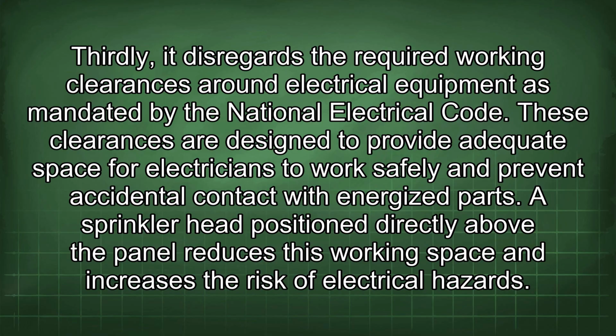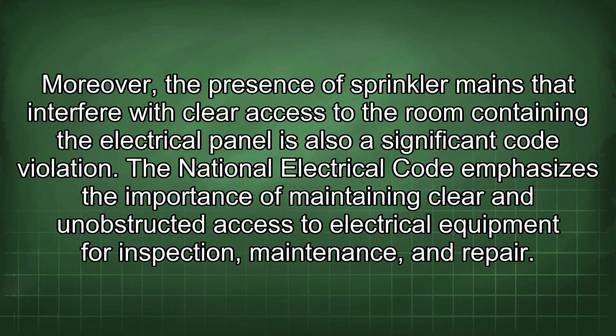A sprinkler head positioned directly above the panel reduces this working space and increases the risk of electrical hazards. Moreover, the presence of sprinkler mains that interfere with clear access to the room containing the electrical panel is also a significant code violation. The National Electrical Code emphasizes the importance of maintaining clear and unobstructed access to electrical equipment for inspection, maintenance, and repair.